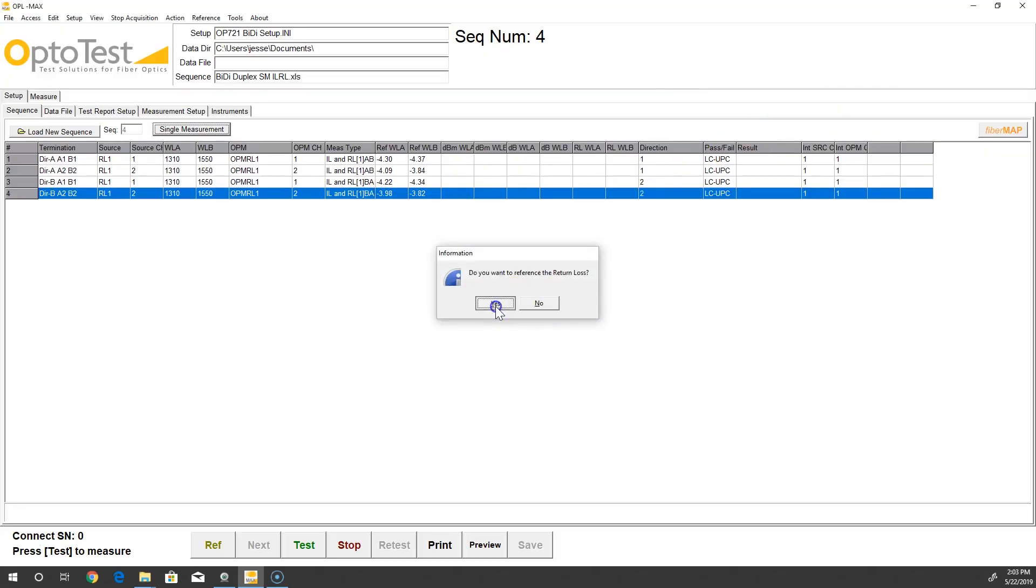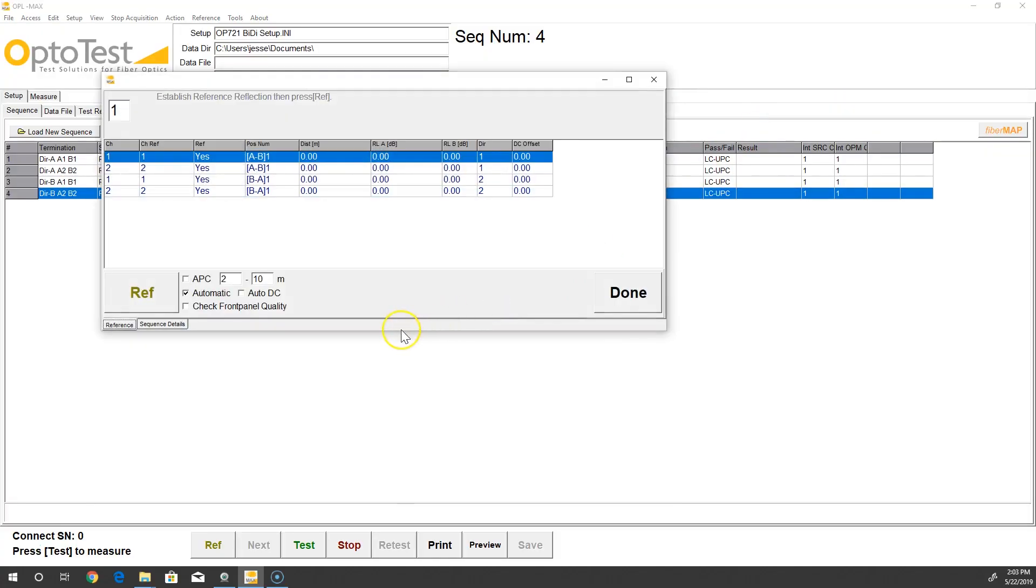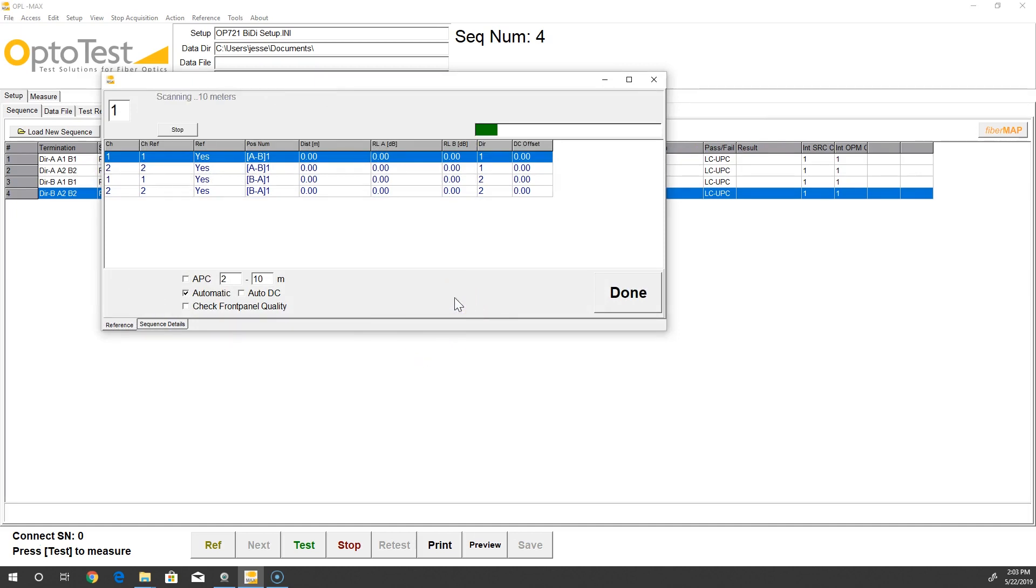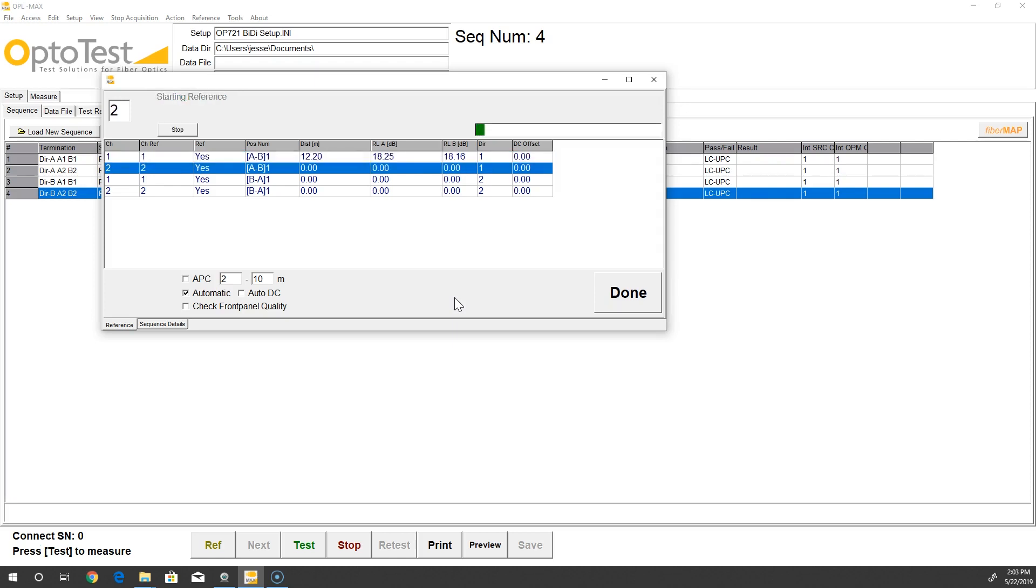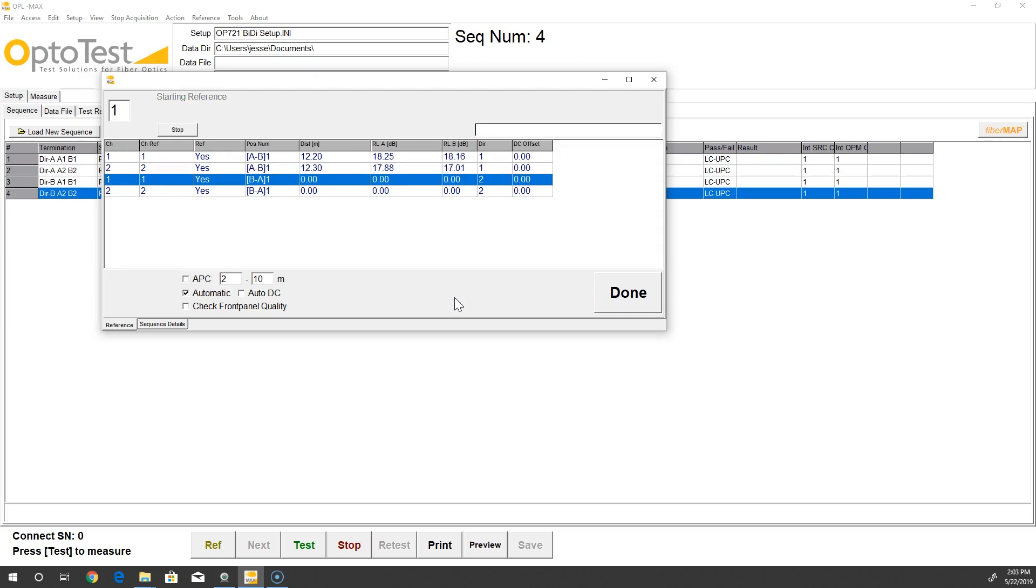The return loss reference is performed in the same order as the previous step. Here we reference each channel individually, but it is possible to copy the reference from the first channel to the second in each direction. Since these are duplex cables, the reference lengths will be approximately the same.